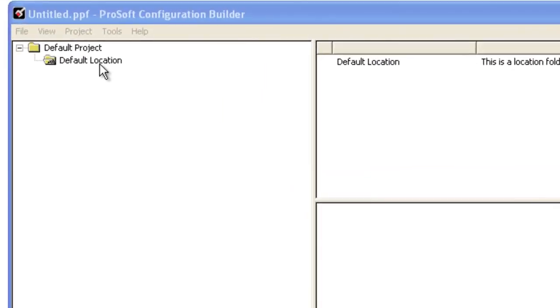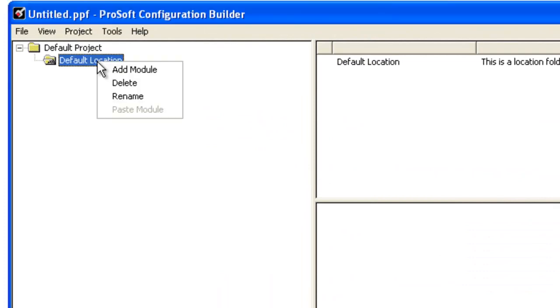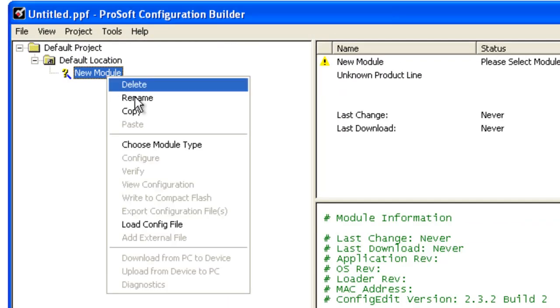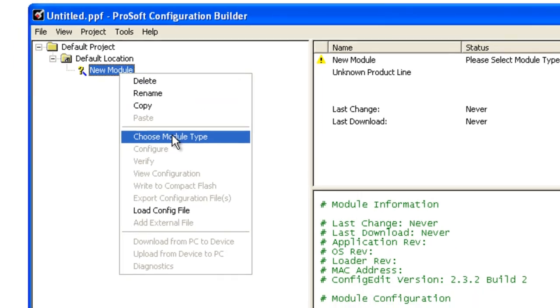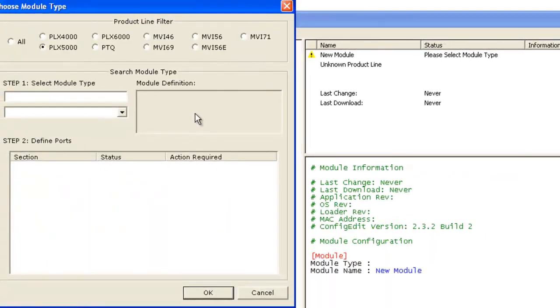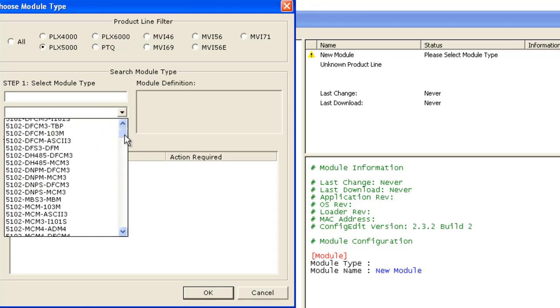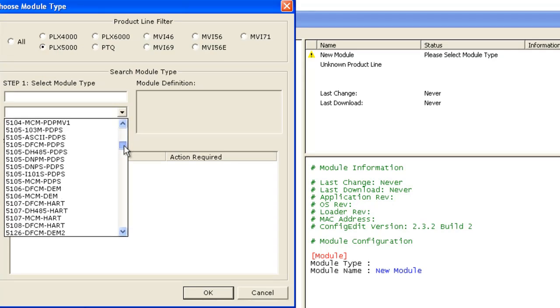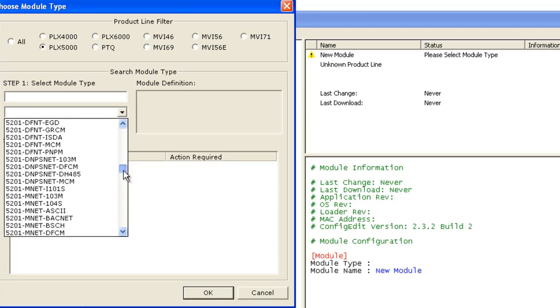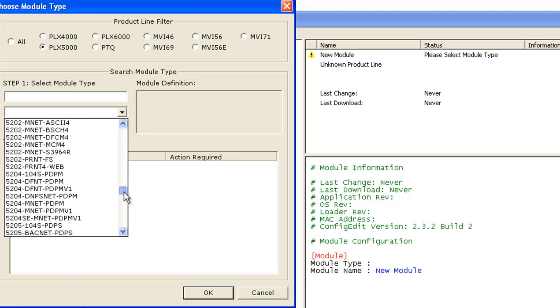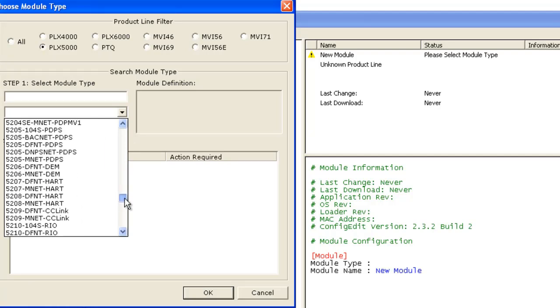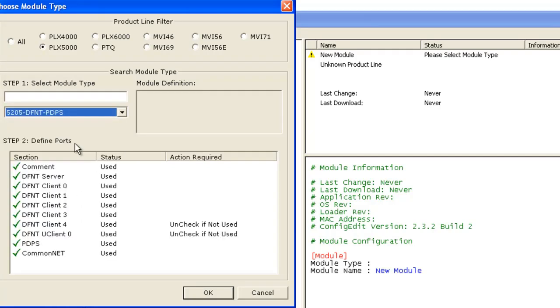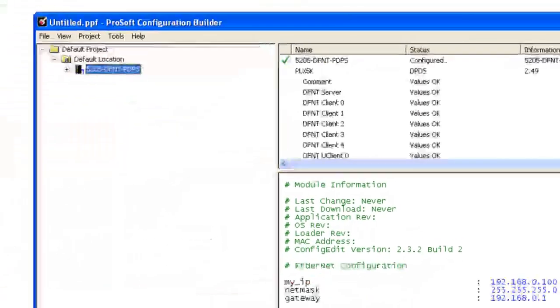So first we're going to go to the default location, right click, add module. From here we're going to right click on the new module, choose module type. On the top is our filter box so we're going to filter by PLX 5000 and go down to our 5205 DFNT PDPS which is the one I'm using. And here it is right here and we'll click OK.